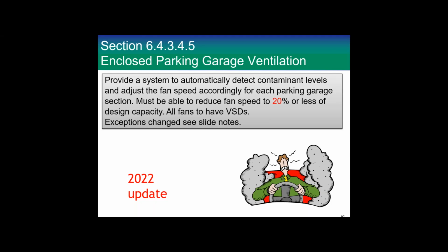Must be able to reduce fan speed to 20% or less of the design capacity, and all the fans must have variable speed drives. Exceptions are shown when you get your slides or if you have them in the notes, but there are some exceptions. So we're going to use a sniffer to decide when we should speed that fan up or slow it down, and we can save some energy that way.